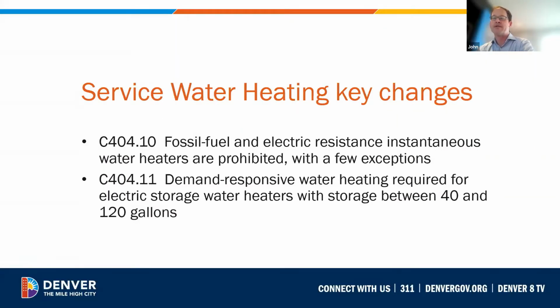Gas water heating is allowed for systems that require water temperature of 141 Fahrenheit or greater, such as commercial dishwashers and laundry that may require higher temperatures. Demand response controls are now required for water heating with storage tanks between 40 and 120 gallons that reset the hot water set point in response to a demand response signal. Water heater location requirements provide electric-ready capability for future installation of heat pump water heaters. And we'll go over those a little bit later.